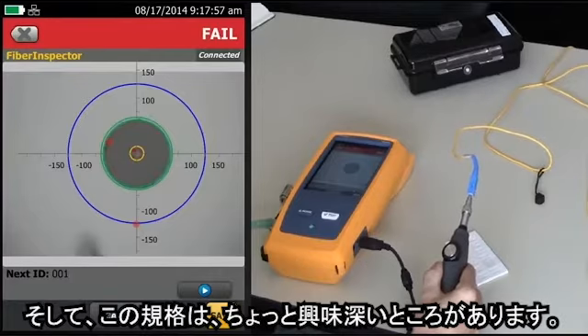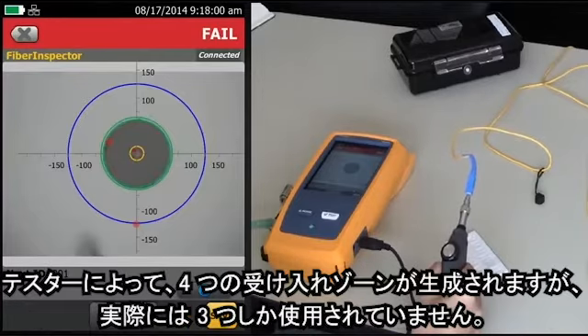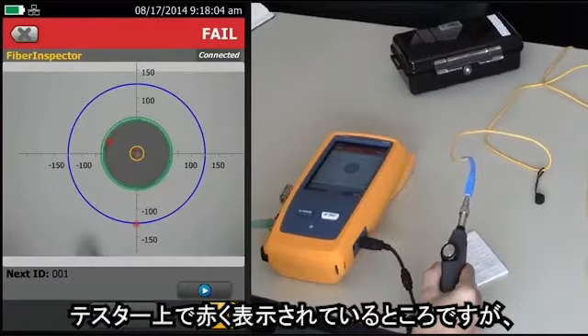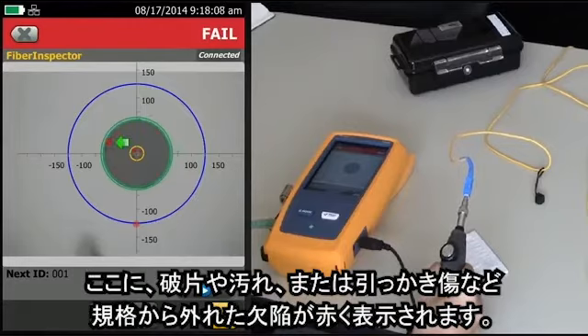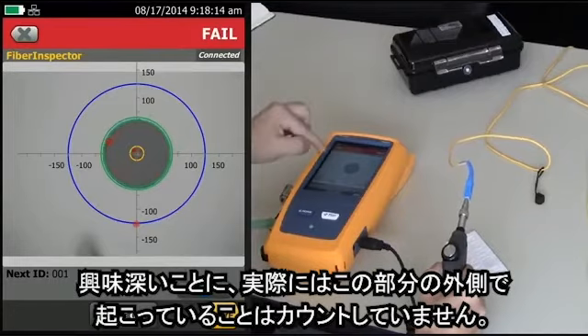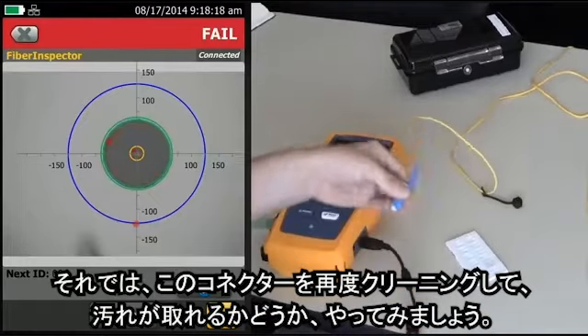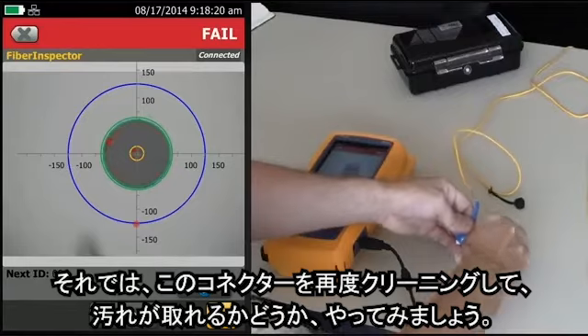And this standard is kind of interesting. It creates 4 zones of acceptance, although only 3 of them are actually used. And on the tester here, where you see the red, that's where there's debris or dirt or a scratch that is outside of that defined standard. Interestingly enough, we don't actually count what's going on the outside here. So let me see if I can do a little bit better job at cleaning up this connector.